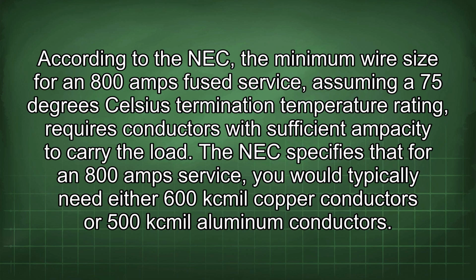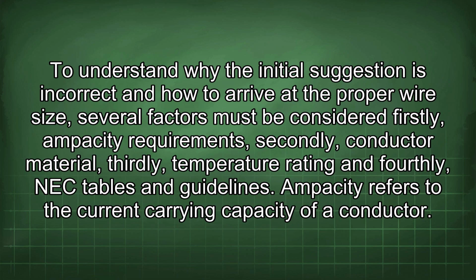The NEC specifies that for an 800 amps service, you would typically need either 600 kcmil copper conductors or 500 kcmil aluminum conductors. To understand why the initial suggestion is incorrect and how to arrive at the proper wire size, several factors must be considered. Firstly, ampacity requirements, secondly, conductor material, thirdly, temperature rating, and fourthly, NEC tables and guidelines. Ampacity refers to the current carrying capacity of a conductor.